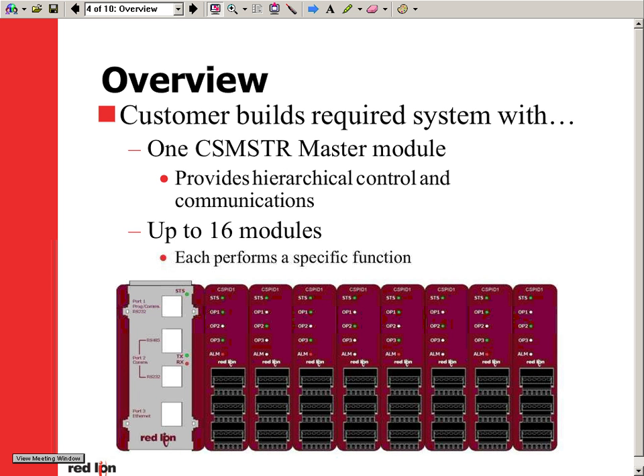The system is built with one master module that provides system power and communications and up to 16 modules. The modular controller has five choices of modules: one loop control, two loop control, eight thermocouple input, eight 4 to 20 milliamp input, and eight 0 to 10 volt input. The last three are for monitoring only.